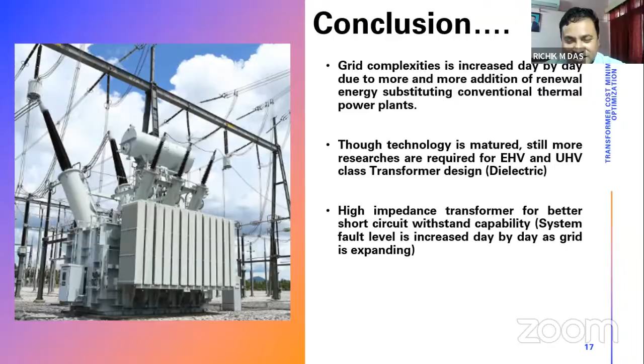High impedance transformers for better short circuit withstand capability may also help reduce the short circuit failure rate, since high impedance means better withstand capability. As our system's fault level increases day by day, this also needs to be looked into. This way we can improve and reduce the cost of transformers. That's all from my side - I kept it precise given the short period of time.